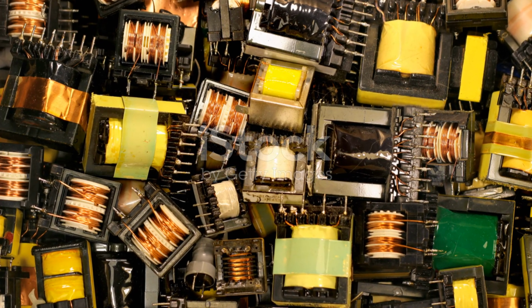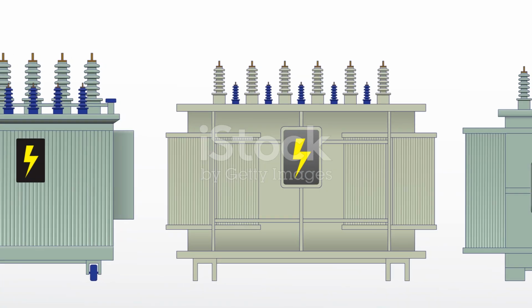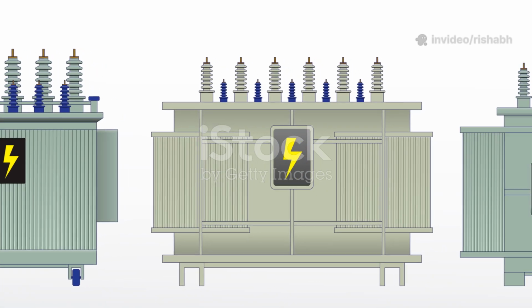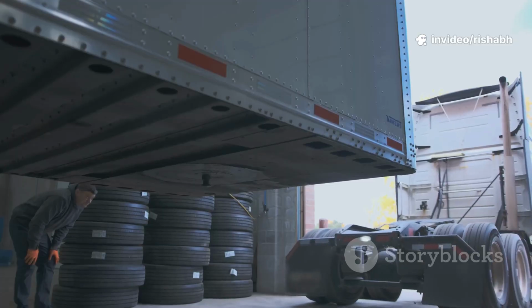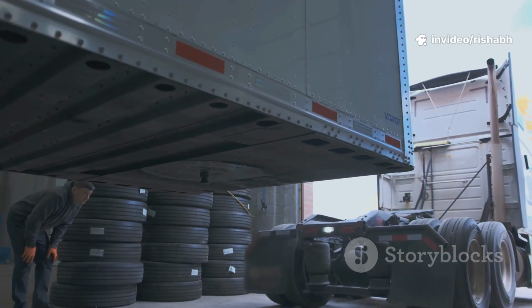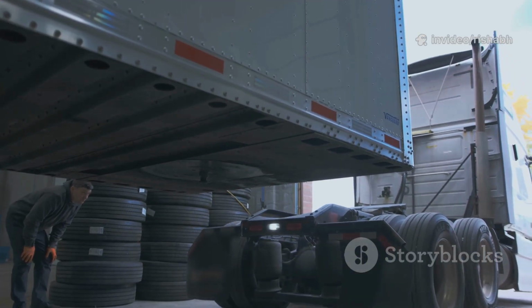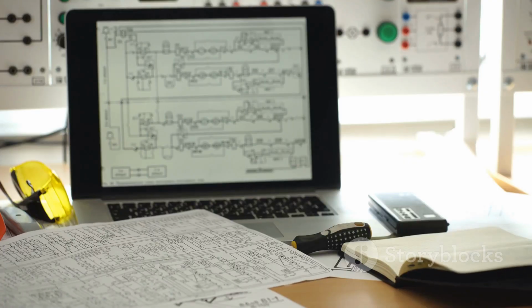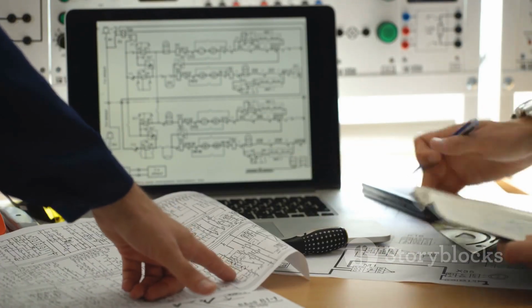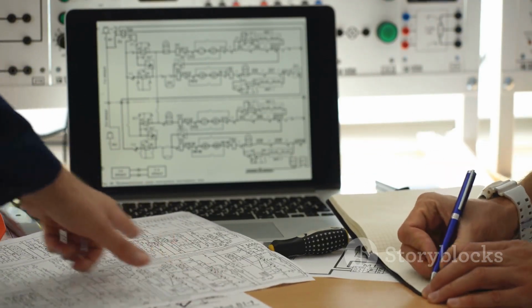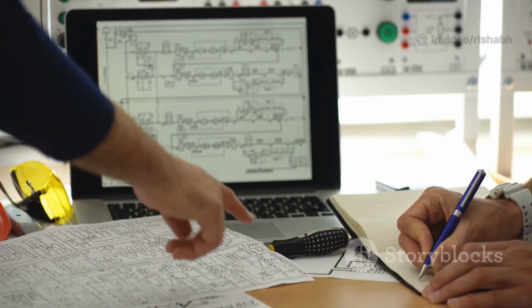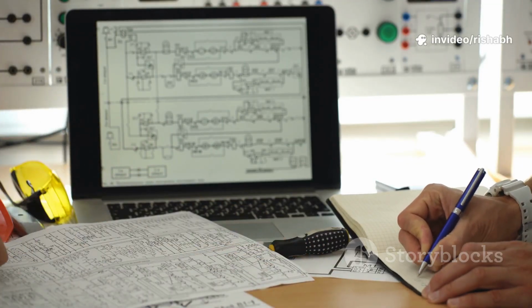It shows the overall dimensions of the transformer, the location of all key components like bushings, radiators, and the tap changer. It details the terminal arrangements, the total weight, and the transport dimensions. This drawing is the primary interface between the manufacturer, the customer, and the civil engineers designing the substation foundation.